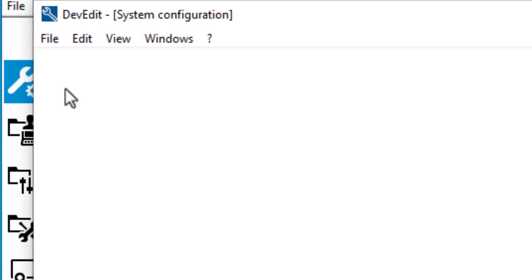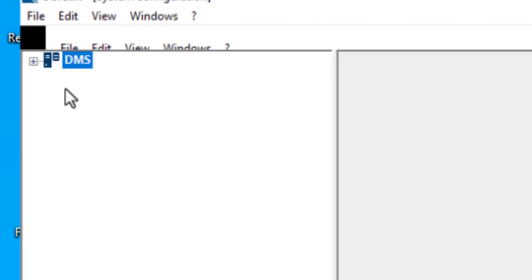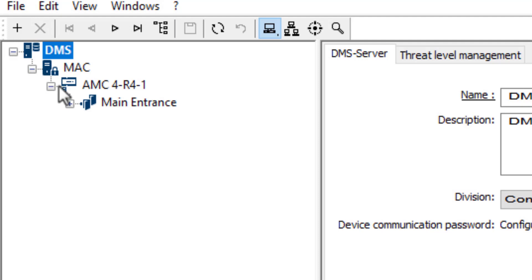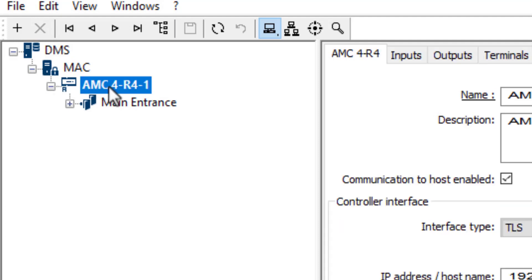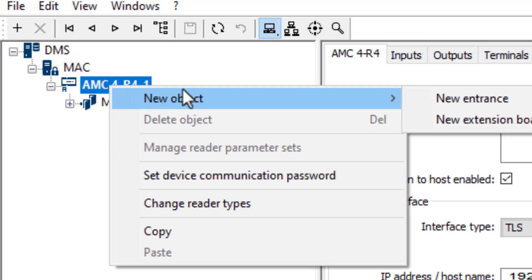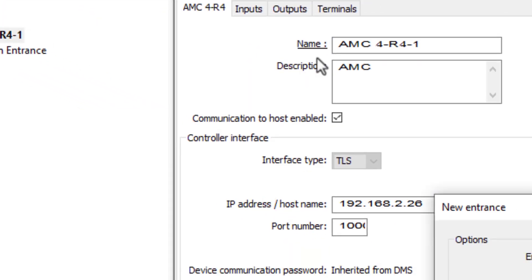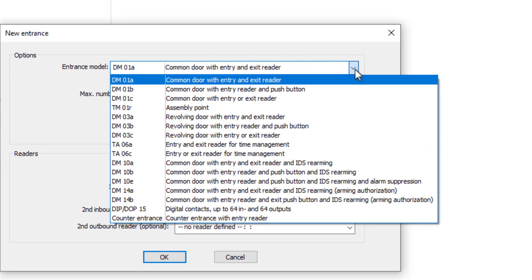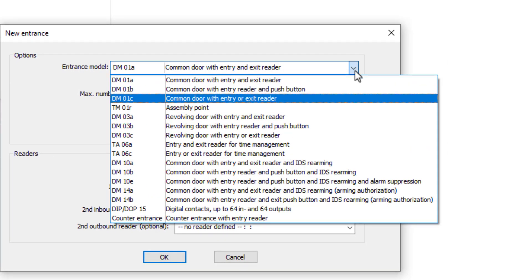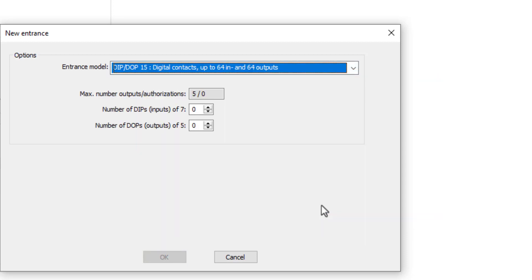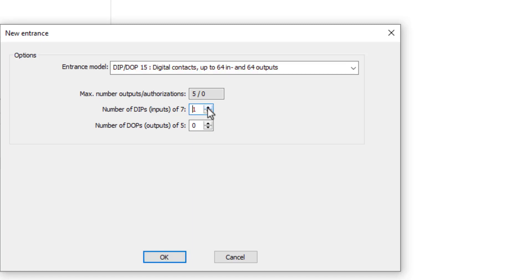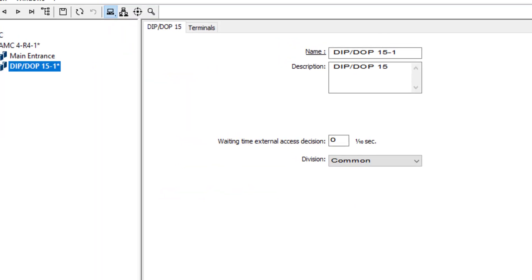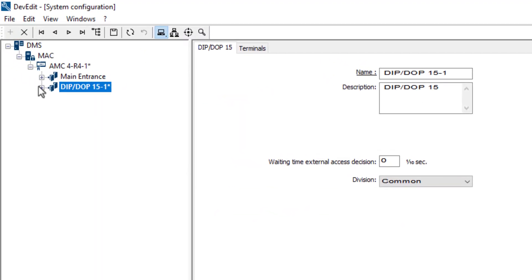The system configuration is started. We right click on the AMC controller to create a new entrance. This will be a special entrance, number 15, DIP-DOP. The system allows 64 DIPs and 64 DOPs, but we need only one of each for this purpose. Let's expand the entrance so that we can see them.